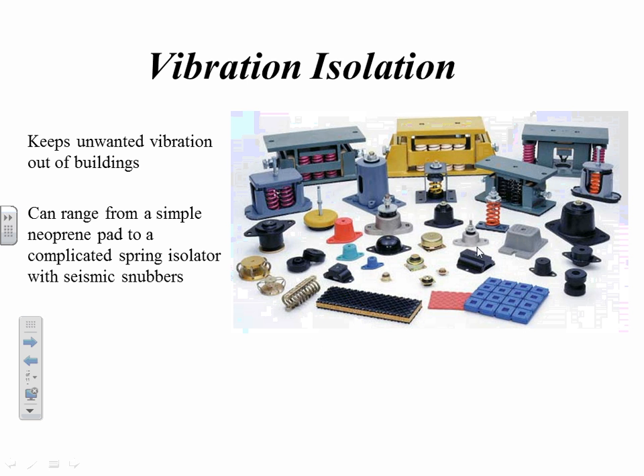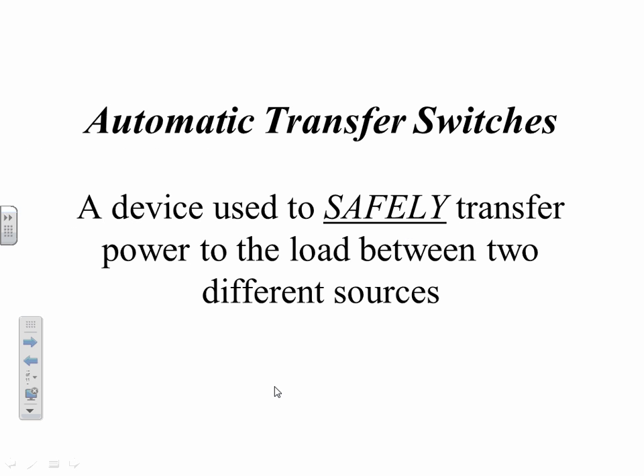And we had some small air-cooled units that we used to put up on these mountaintop sites when we only had like 15 kilowatts or so. And we used to call this waffle pad, because it's got cork in the middle and neoprene on both sides, and it's kind of a rough fit. But it worked really well for those types of sets, and we just run some of that stuff underneath the skid of the generator set, and then we bolt through it to keep the generator from running around. Keep it in place.